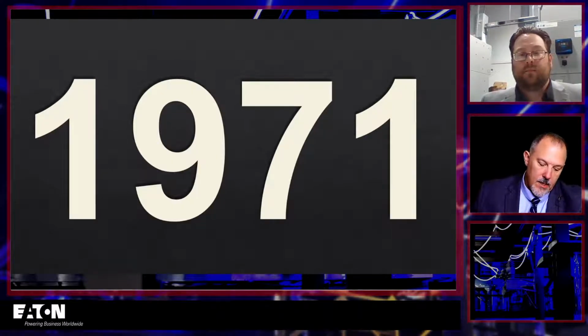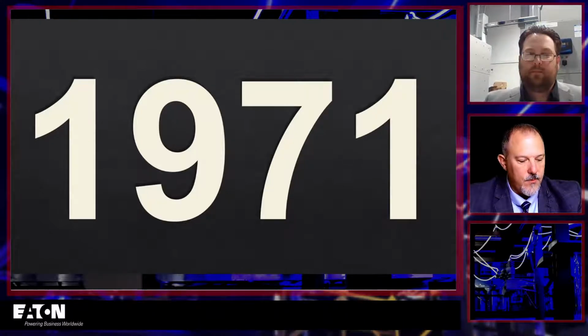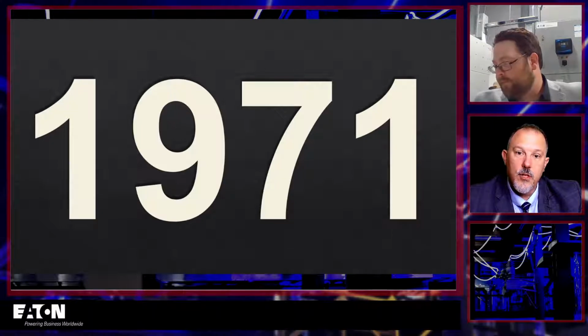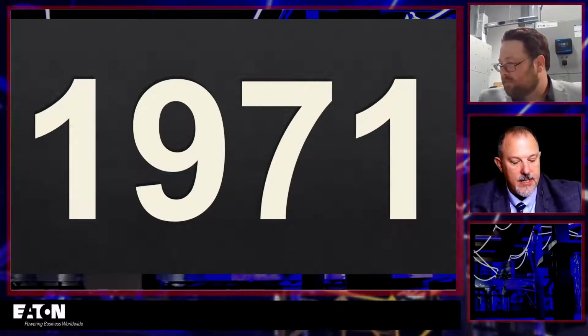But 1971 is when it went in the National Electrical Code, and I've got the preprint version from 1971 which gives us the reasoning for why it went in the code. So I'll just read this, Michael, and I'll give you the language that went in the code, which is not too far off from where we're at today. Ground fault protection of equipment shall be provided for grounded electrical services. So if it's ungrounded, I don't need it, right? Of more than 150 volts to ground, but not exceeding 600 volts phase to phase, for any service disconnecting means rated 1,000 amps or more. So the 1,000 amps went in 1971 from the get-go. And most of the other stuff is pretty much the same.